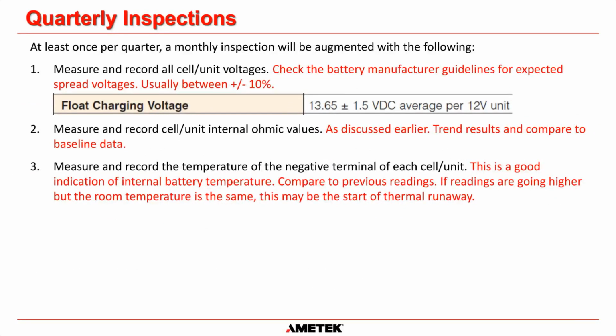For the quarterly inspection, they want you to do everything that you just did on the monthly, and then measure and record all cell unit voltages. Once again, you have to check the battery manufacturer guidelines for the expected voltage spread, and that's usually between plus or minus 10%.